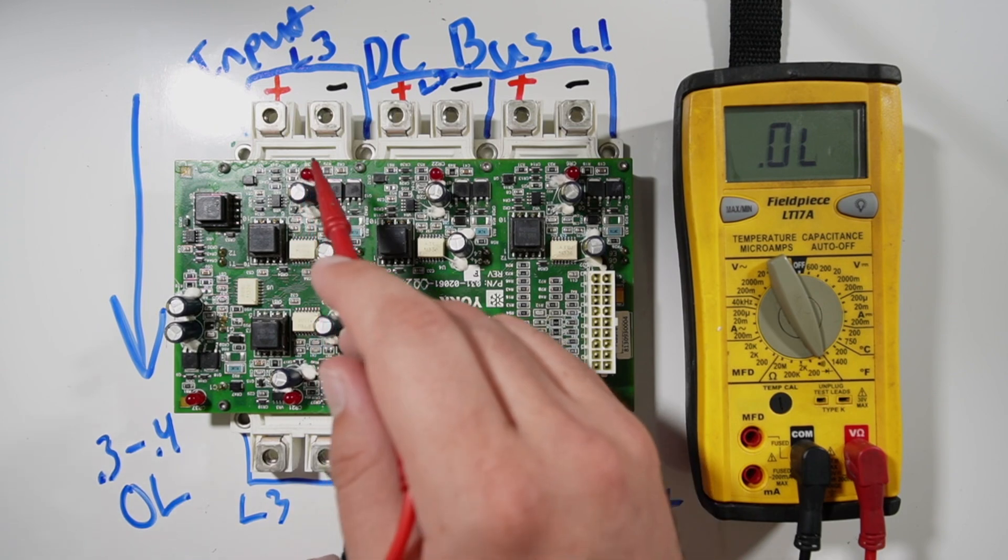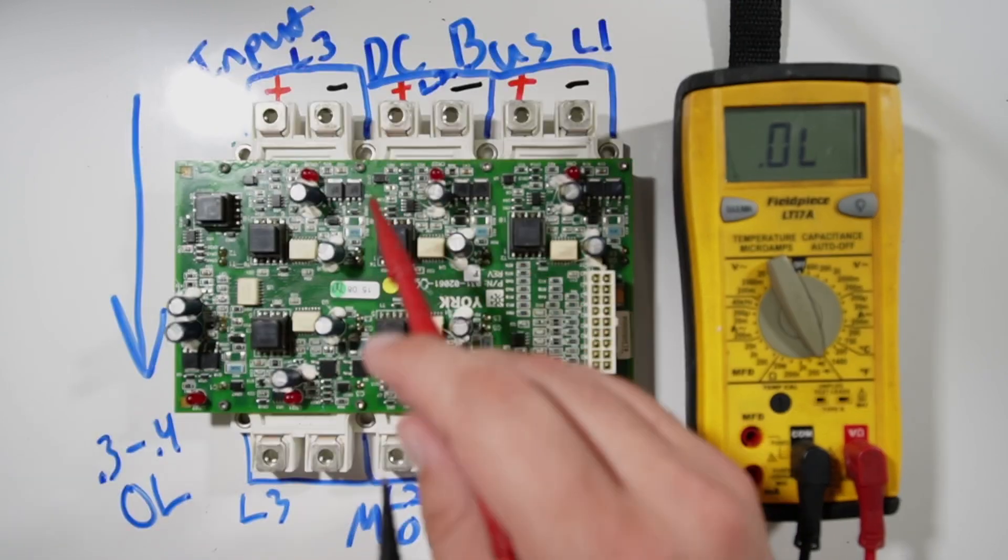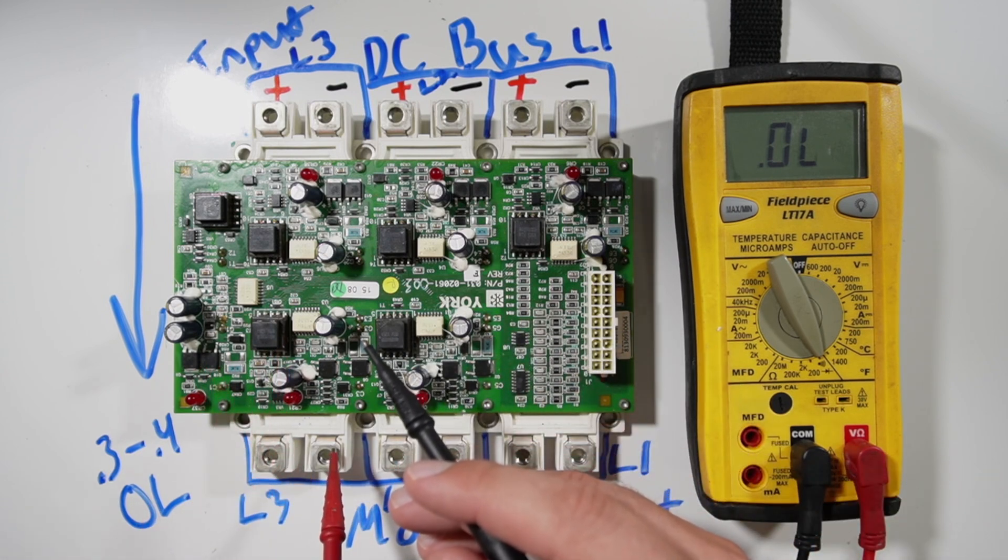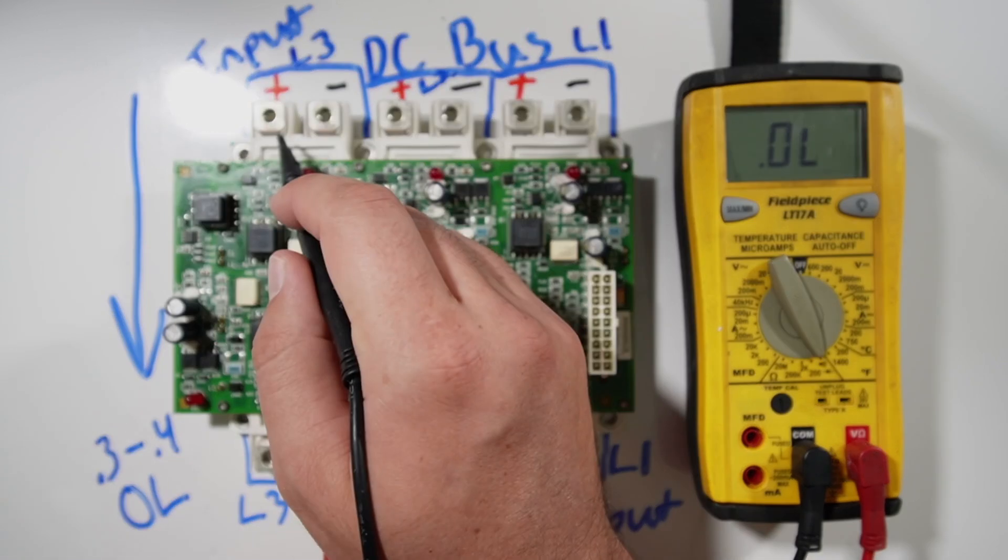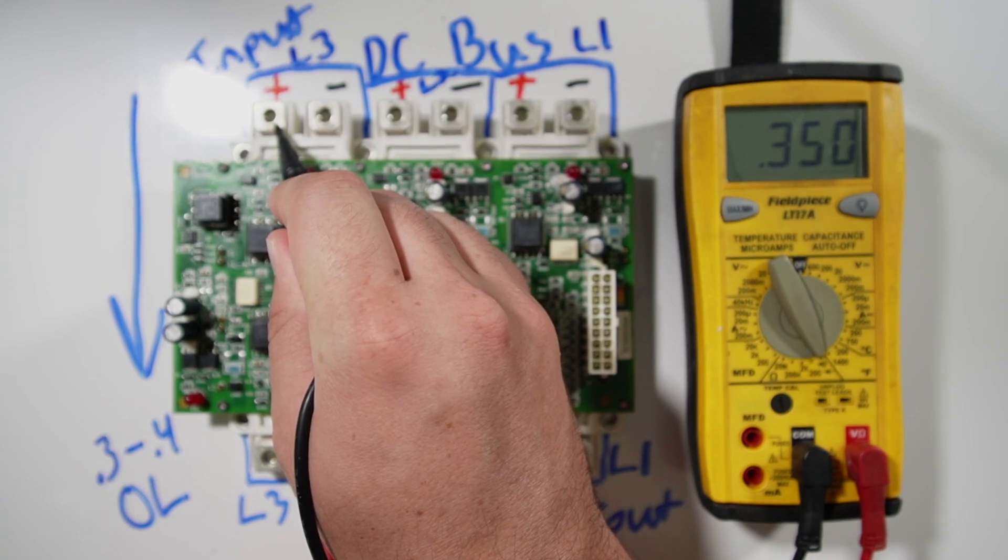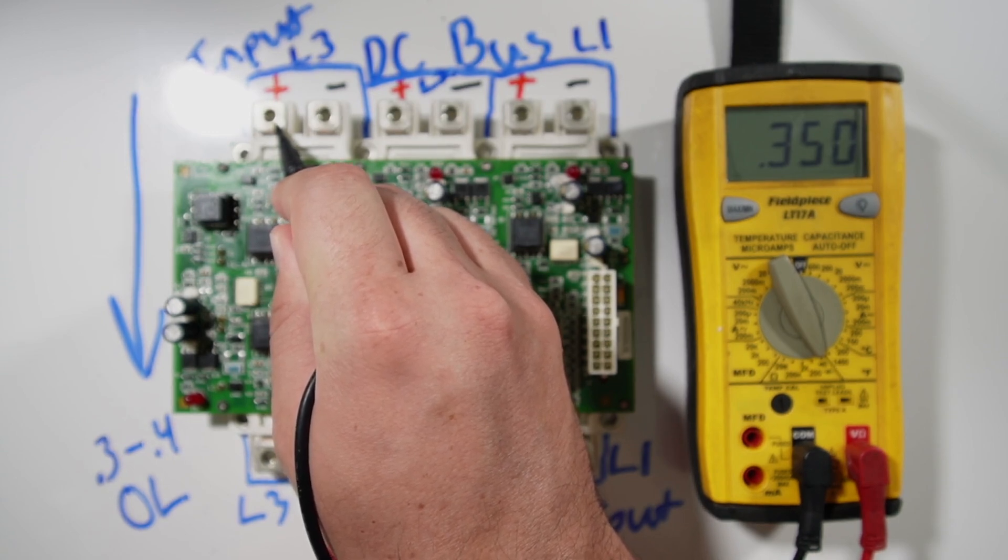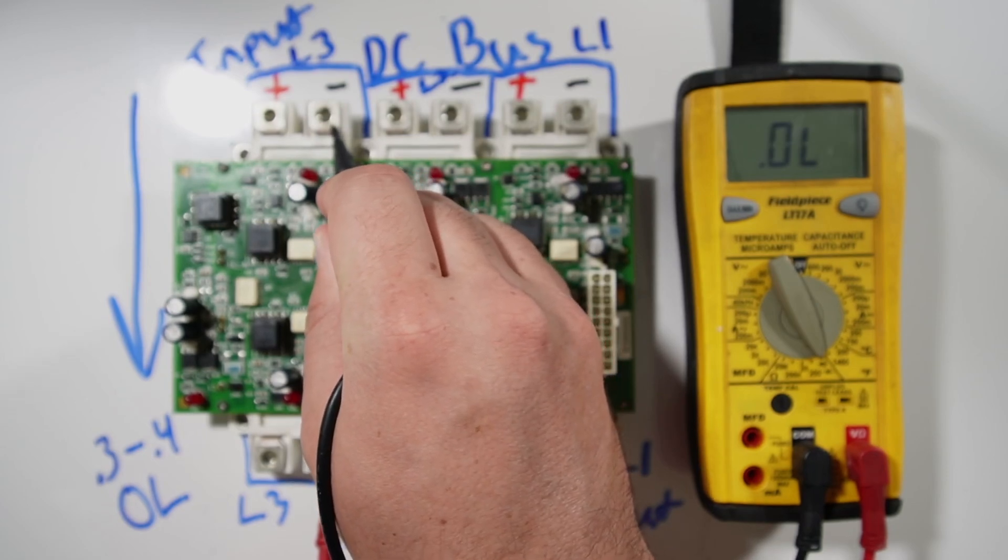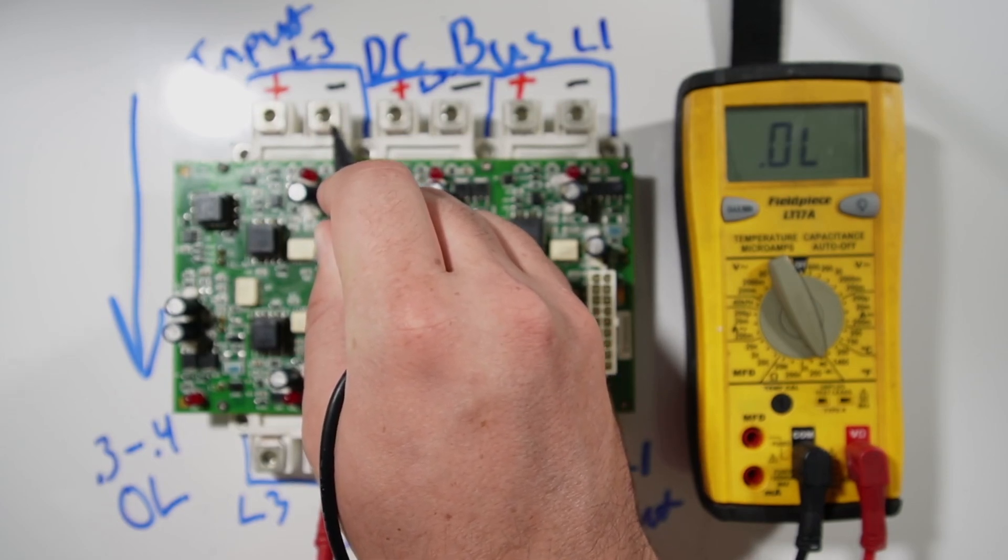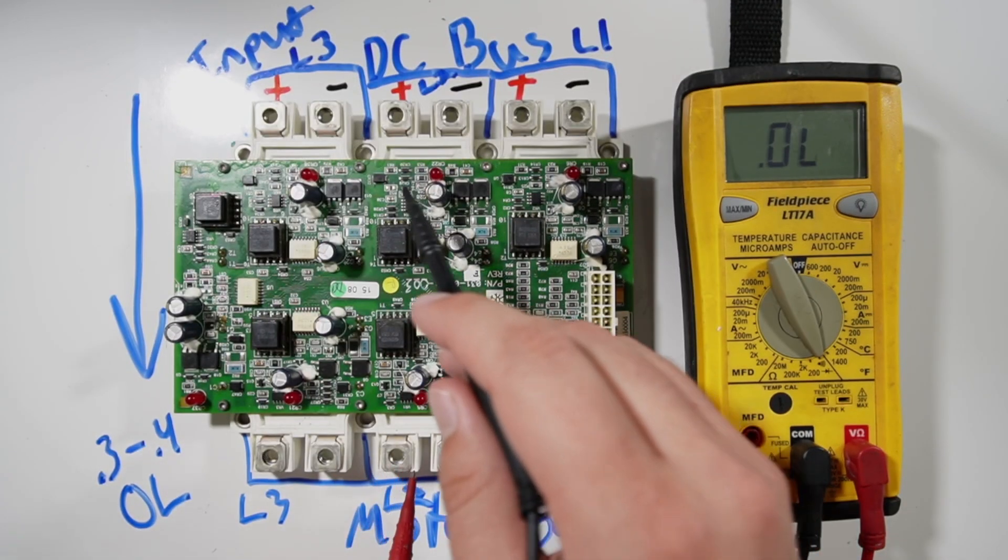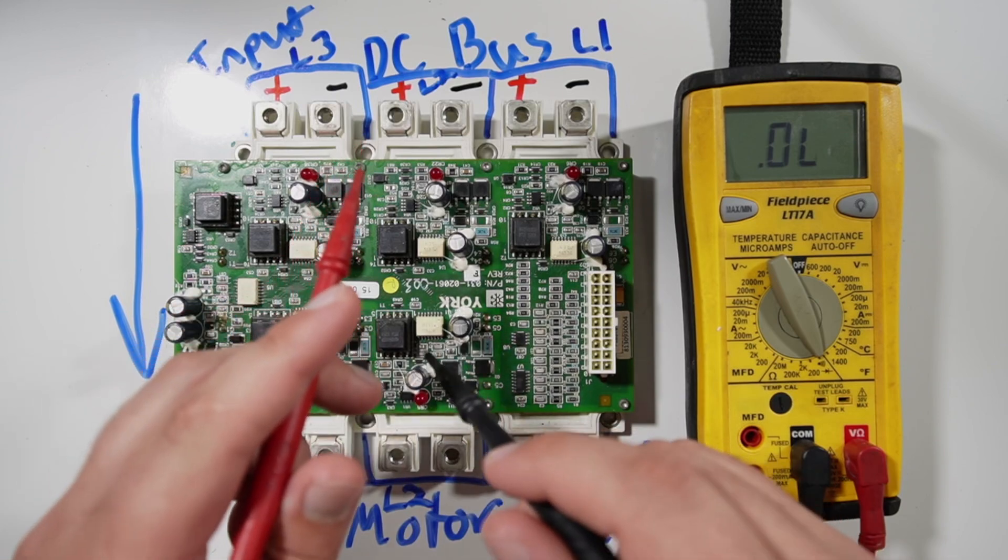Depending on your preference, you can either move over and test the next one, or I like to finish a full gate at a time. To do that, we now need to reverse our leads. Our red lead will then go on the output side. We'll use our black lead. Earlier this was OL. Now we have a reading of 0.35 on the positive. And our negative terminal gives us OL. That's a good test. That is exactly what I want to see for this gate. And we're going to do that same exact process on all three of these.